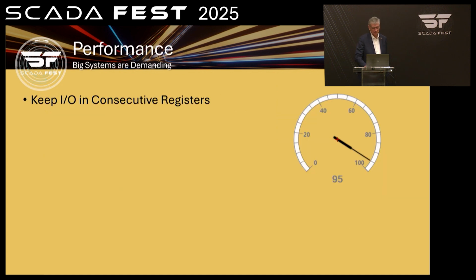Performance. This is one I've seen a lot of, especially in Modbus - it's not strictly limited to Modbus, but people don't put their I/O in consecutive registers. They tend to sometimes just scatter them all over the memory map. Every time they're in a different place in the memory map, it's a separate read out to the device. And if you're going over a cellular connection or a serial connection, even worse - every block requires a separate communication packet going out to it. So it takes a long time to get your updates. If they're all in one block, it goes much faster.